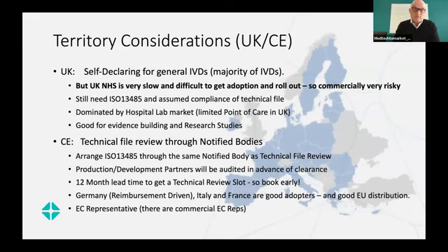But typically, in order to book in with UL or BSI, I would recommend that you have your 13485 accreditation through the same notified body. So check with them first. But also, there's about a 12-month lead time to book a slot for that technical file review. So book early, don't wait till you finish the project to book that slot.